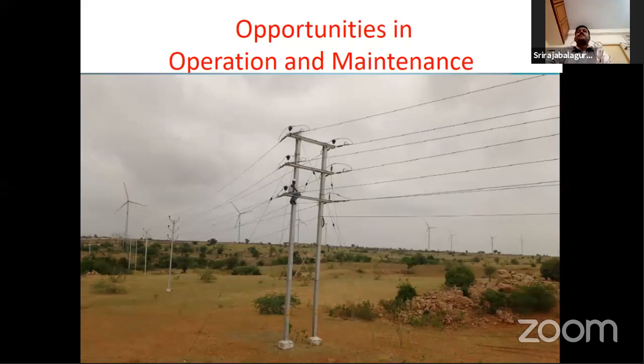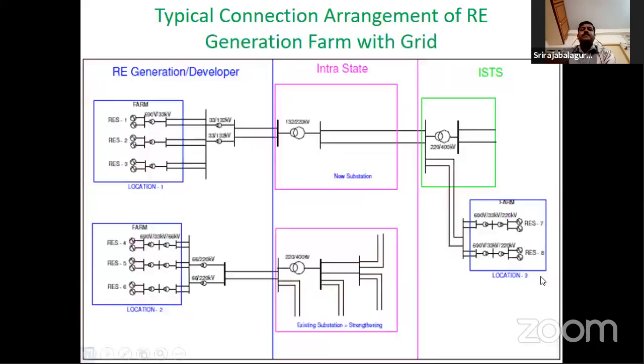So you can see this. How is the typical wind farm? You can see this RE generator. Here the generation voltage is 690 volts. Nowadays we are getting 690 volts. Previously, the old machines had 440 like that, so that is the older one. But now the terminal voltage, that is the generation voltage, is 690 volts. This 690 volts is stepped up to 11 kV. Next slide. Next.